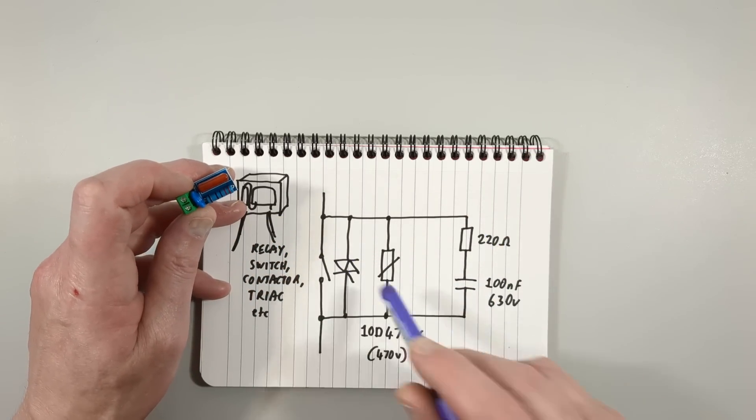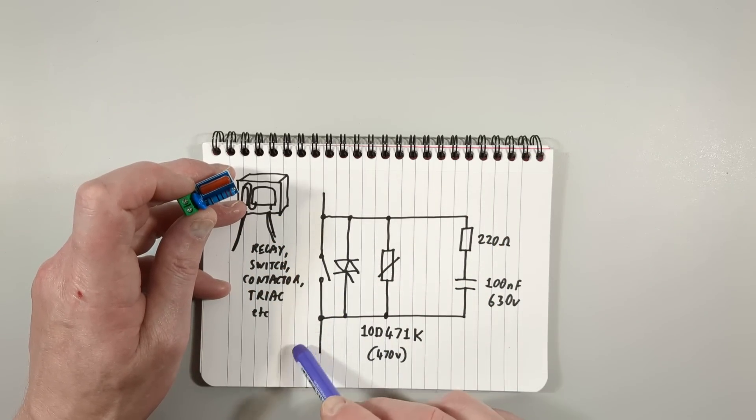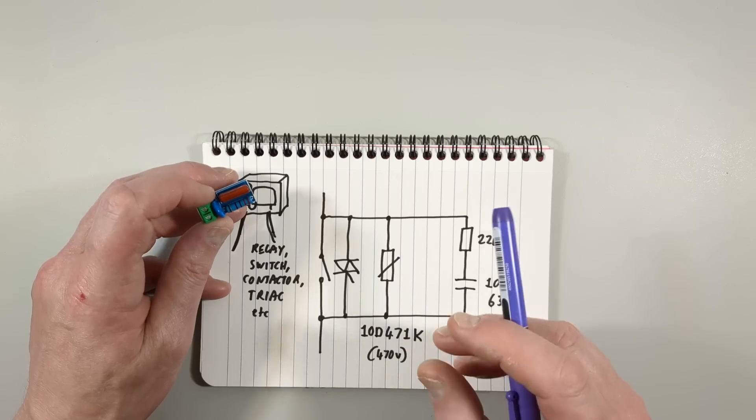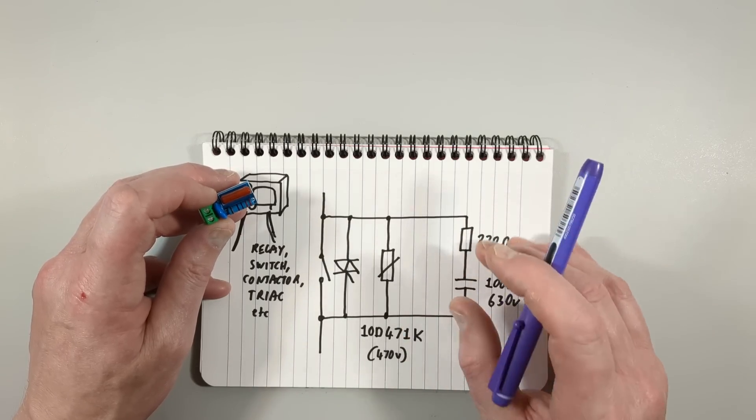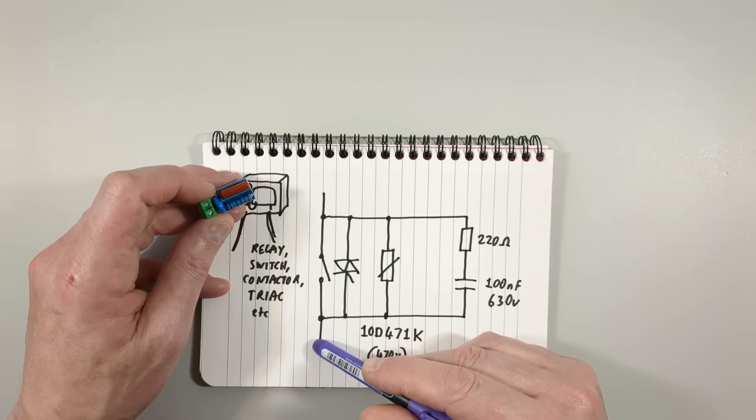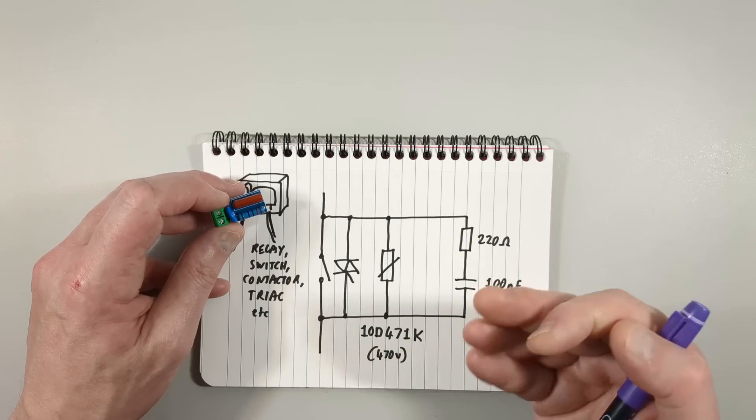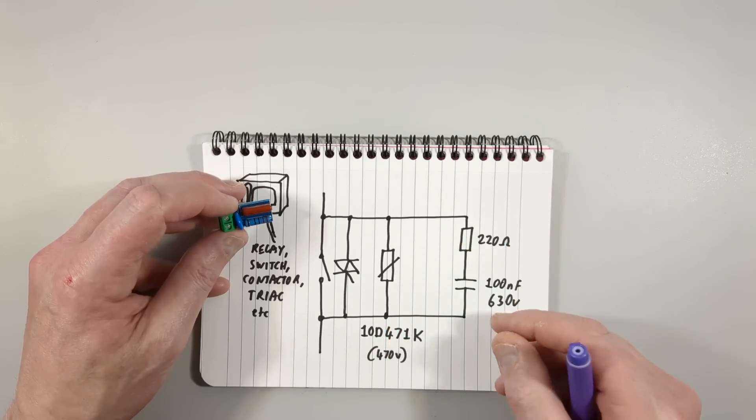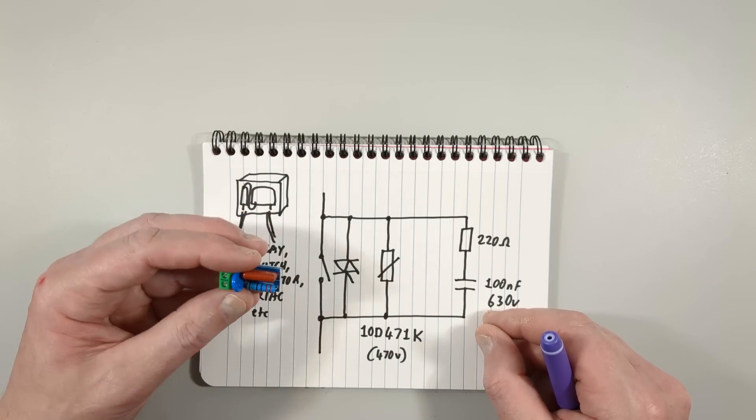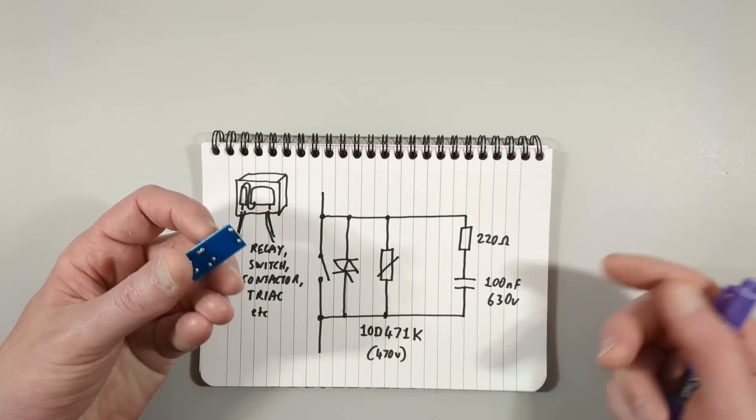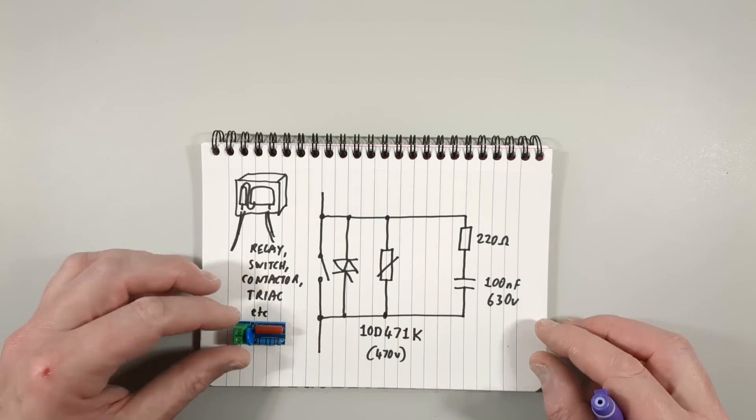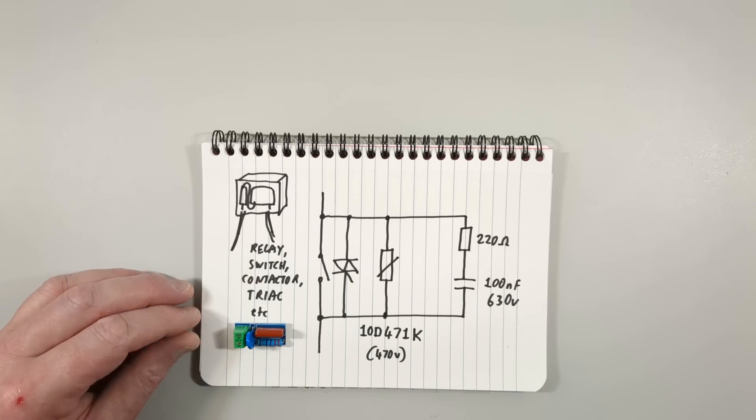You also have to keep in mind when you put a snubber network across a contact that the load it's driving - say for instance a super low current load like a solenoid coil - it may pass enough current to stop that solenoid coil from dropping out. But very useful things, they're absolutely an essential part of industrial control electrical and electronic equipment.